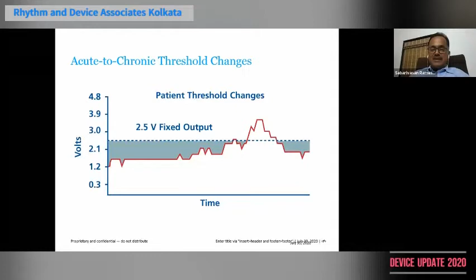we have given a pacemaker and the pacemaker is supposed to capture. If it is not capturing, whatever algorithms this pacemaker is carrying out are of no use, because it is not able to capture. The basic objective of the pacemaker is to capture and this is not happening. So loss of capture is something which is a problem.